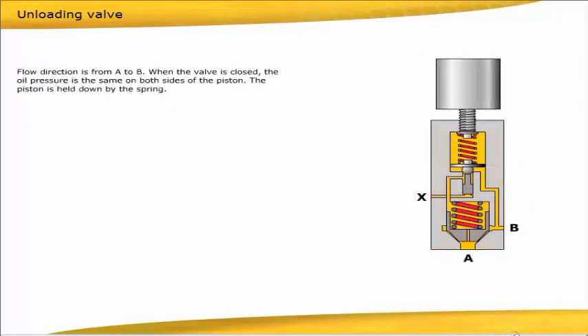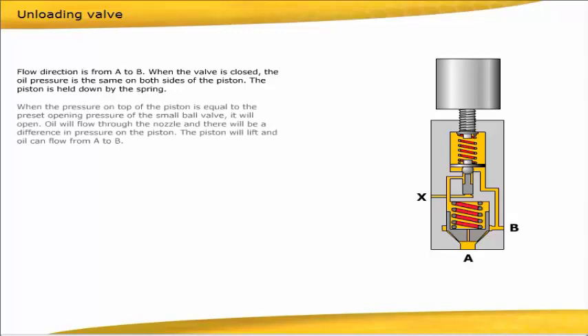When the valve is closed, the oil pressure is the same on both sides of the piston. The piston is held down by the spring. When the pressure on top of the piston is equal to the preset opening pressure of the small ball valve, it will open. Oil will flow through the nozzle, and there will be a difference in pressure on the piston. The piston will lift.